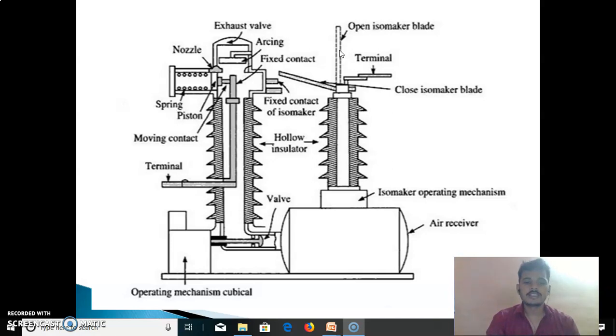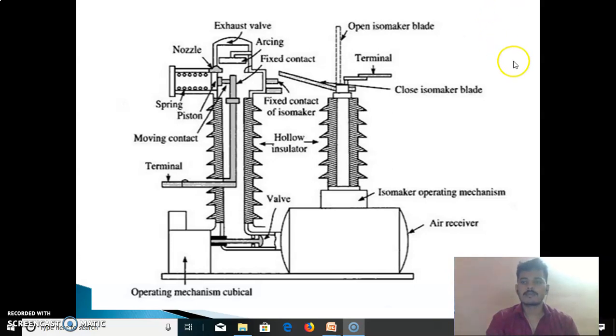The disadvantages of the air blast circuit breaker: First, an air compressor plant has to be installed and maintained. Second, upon arc interruption, the air blast circuit breaker produces a high level of noise when air is discharged to the open atmosphere. Third, there is the problem of restriking voltage.